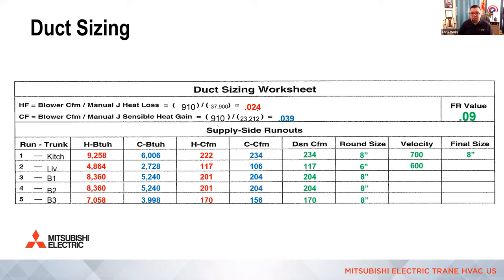We do the same for the rest of them. You can see that 6 inches is a little small, little short. If it's short, maybe below that's okay. We might want to downsize that to a 5-inch. I have a feeling at 117 CFM, right, for a 5-inch duct, the velocity is going to be too high in order to actually design. Yeah, it's going to be around 800 feet per minute. So we could go to a 5-inch in that example. If it's short, maybe keeping a 6-inch is okay.